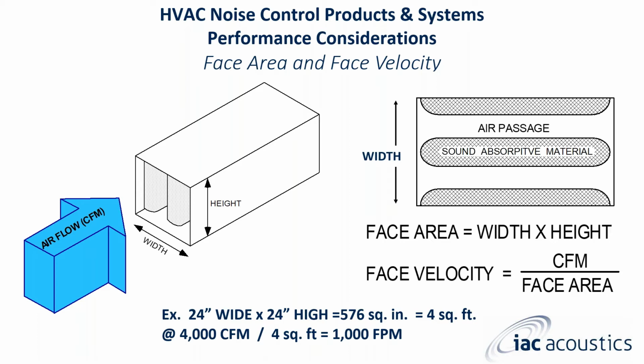I always say this just to make sure, because I've had some people get it wrong: make sure you utilize the square feet, not the square inches, when you're dividing with the CFM to get your face velocity. You will get a skewed number if you do.